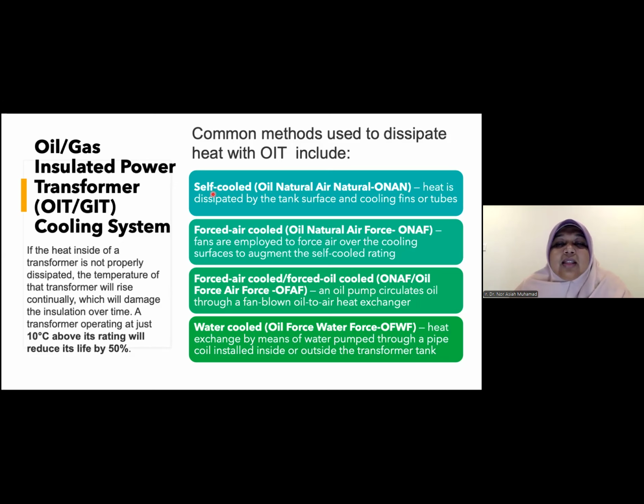Self-cooling means oil natural, air natural, which is the transformer without any fan, only having fins or tubes. So it will be cooled naturally. Then we have forced air cooling, which is oil natural, air forced, where the oil circulates naturally. The higher temperature oil is at the top. Then if we go to the fin, we have a fan at the fin to make it cool faster.